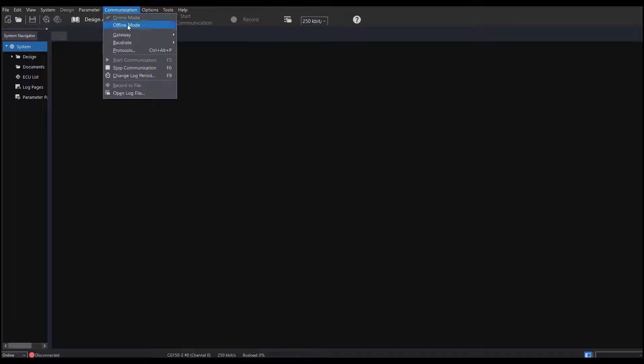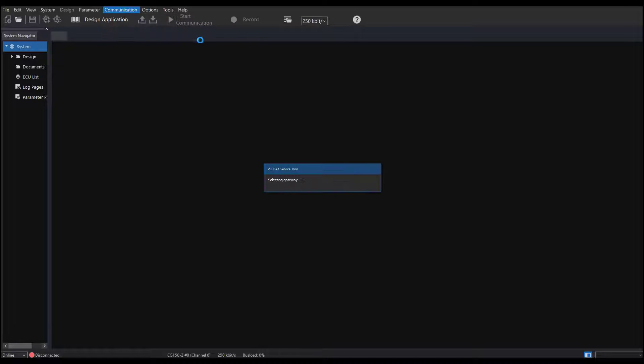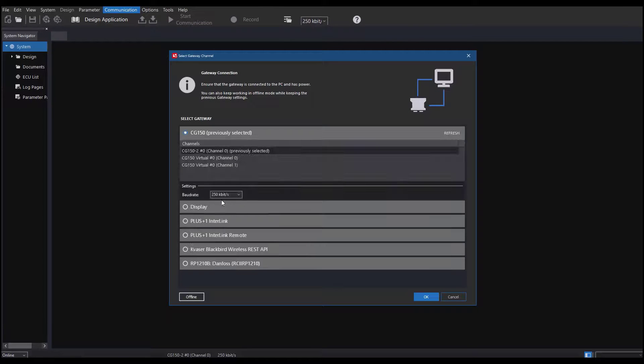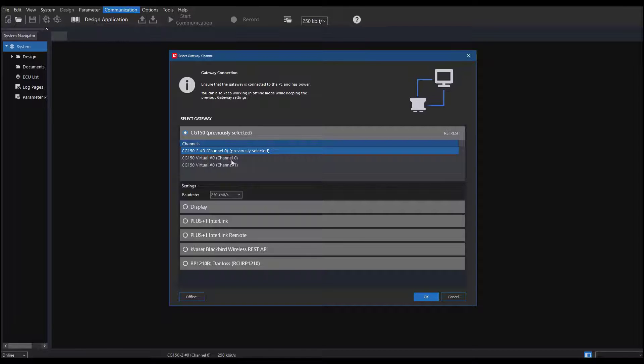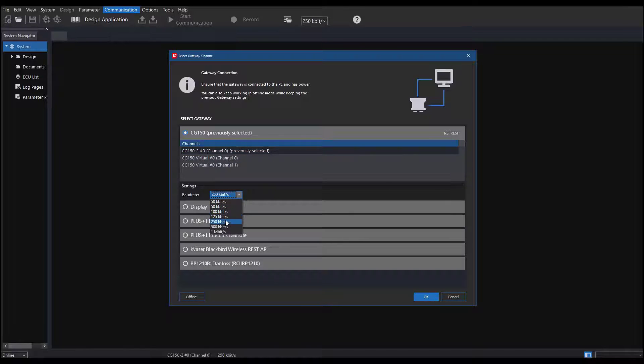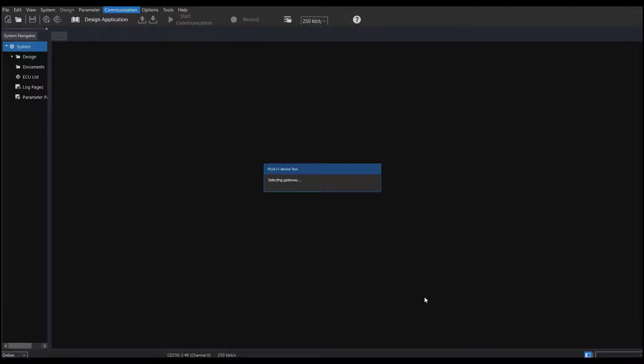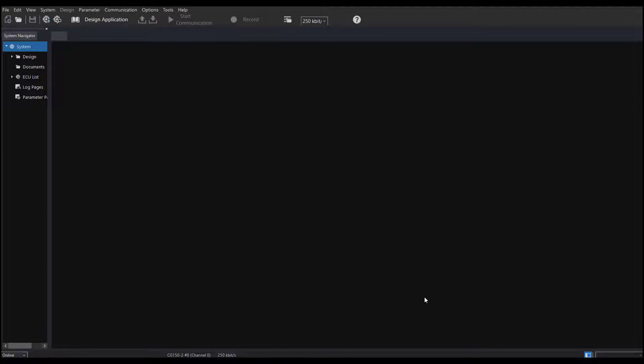If for any reason the service tool does not connect and the select gateway window does not open automatically, go to the Communications menu and click on Gateway, then select Gateway. Select the CG150 and be sure to select a channel that does not say Virtual. Make sure the baud rate of the CAN bus you are connecting to is correct, then click OK. The service tool will attempt again to connect and scan the system for CAN devices.